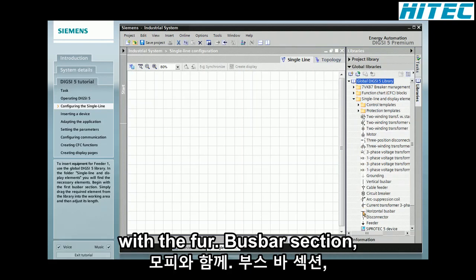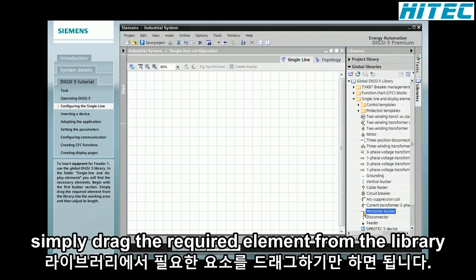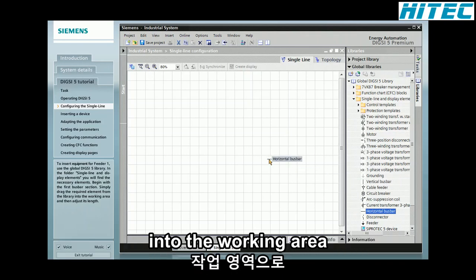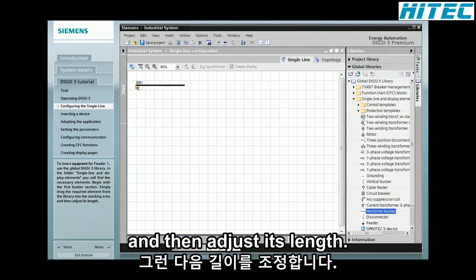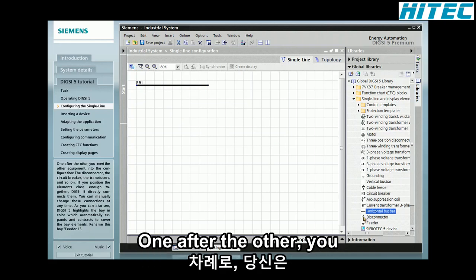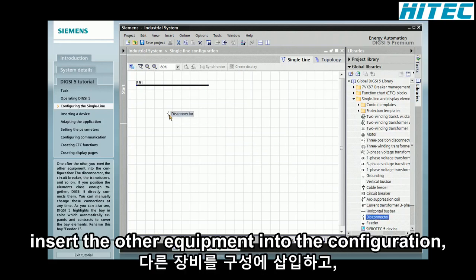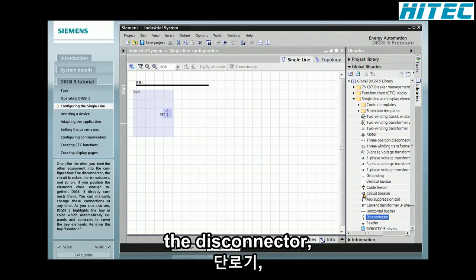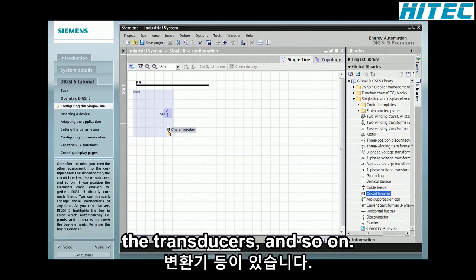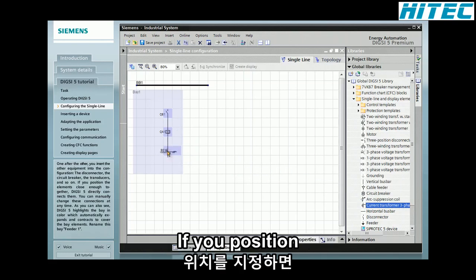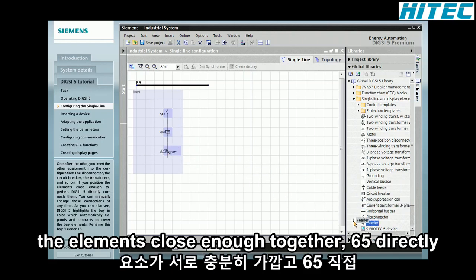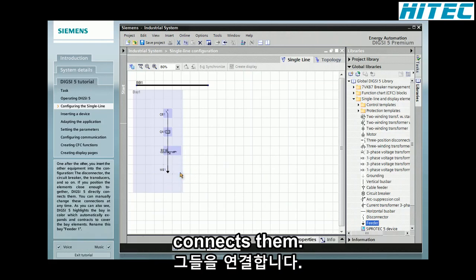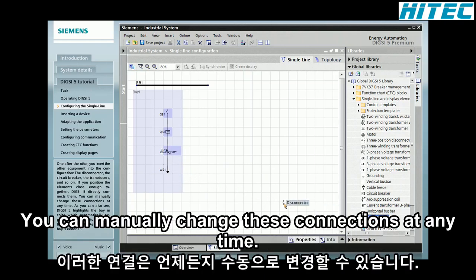Begin with the first busbar section. Simply drag the required element from the library into the working area and then adjust its length. One after the other, you insert the other equipment into the configuration: the disconnector, the circuit breaker, the transducers, and so on. If you position the elements close enough together, DIGSI 5 directly connects them. You can manually change these connections at any time.